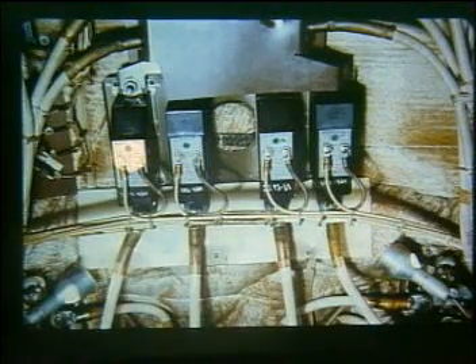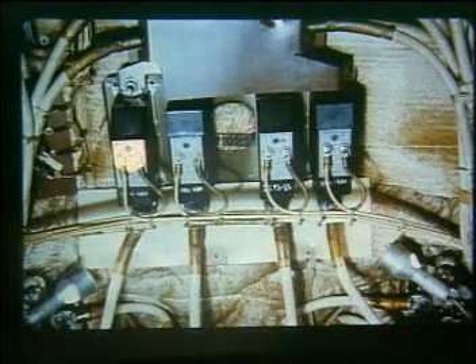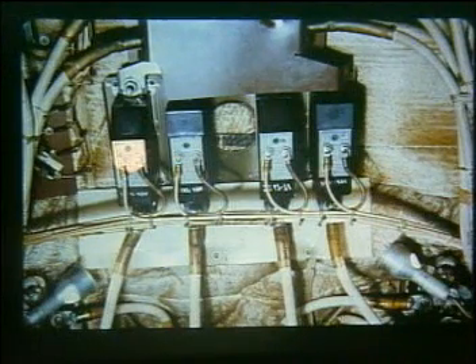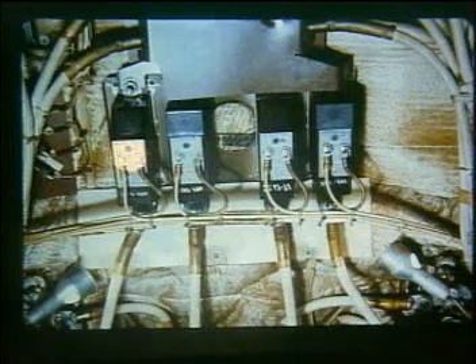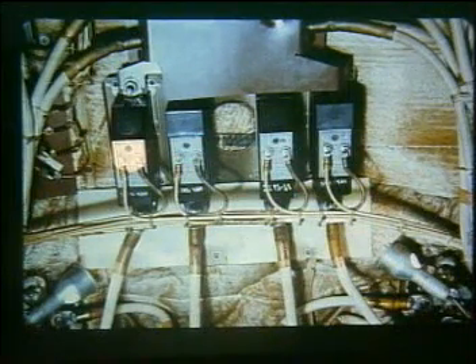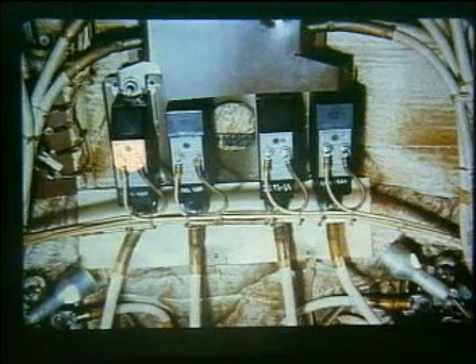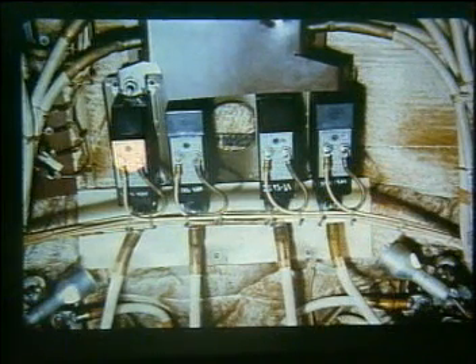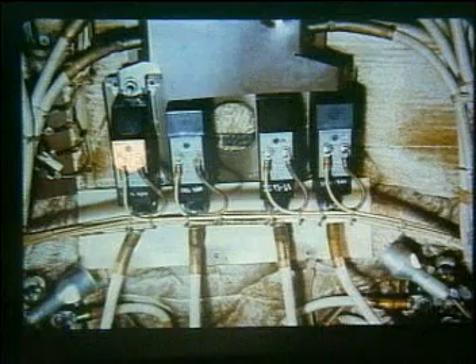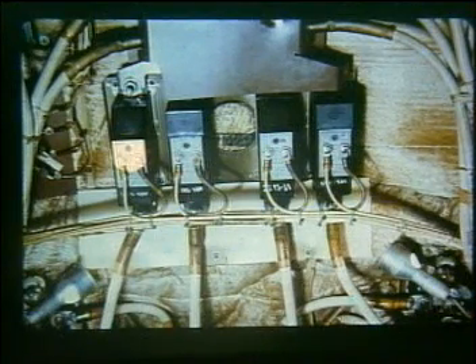The reverse current circuit breaker is located in the top of the main junction box. A small round indicator window on the top of the circuit breaker will show yellow, thus indicating the circuit breaker has been tripped, killing the generator output. This circuit breaker can be manually reset by depressing a reset switch located under a soft rubber cover on the forward end of the circuit breaker.